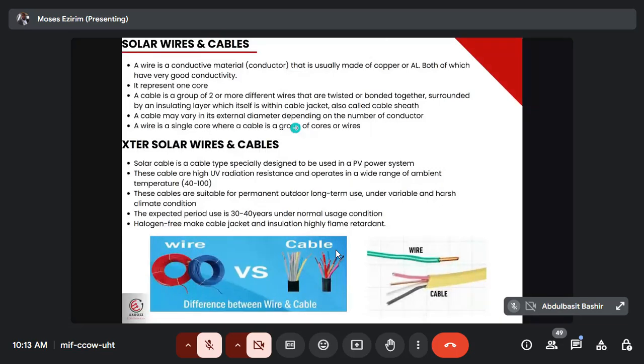Now, for solar installation, especially the DC cable which is the solar cable, ensure you identify all these characteristics. Don't use any other cable. Your normal AC cable cannot be used in place of a DC cable, because of characteristics not exhibited by normal AC cables. Solar cables are a cable type specially designed to be used in a PV solar system, designed specifically for that system, and we're going to see the reason why.